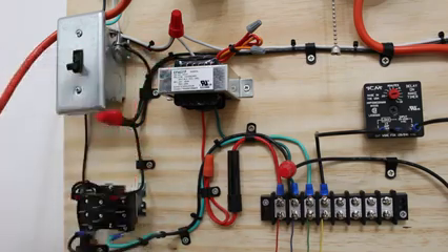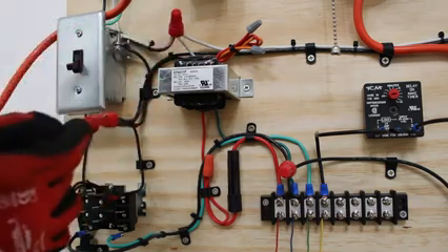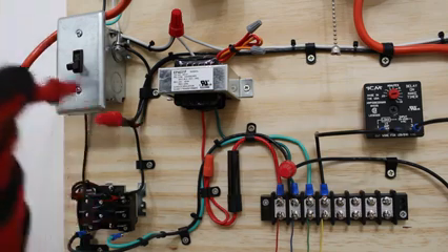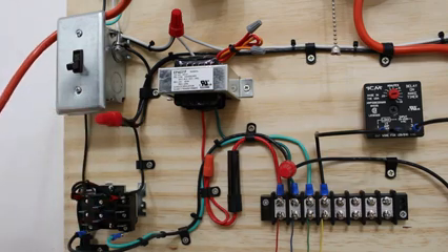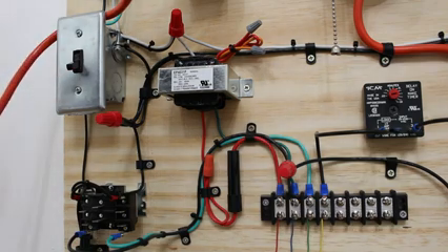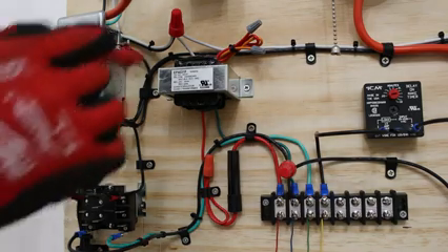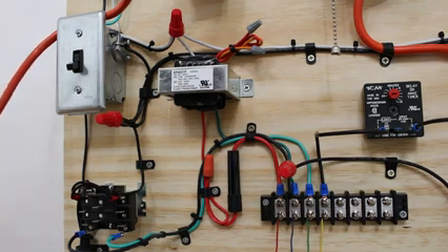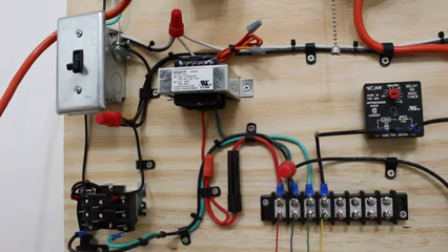It's all about making sure if you have your primary and secondary voltage. So if you don't have voltage at your primary, you need to stop what you're doing. It has nothing to do with the transformer. You need to look into the incoming power to the system. That means you're not getting incoming power. You got to follow those wires. So those are a couple tips, but pretty much that's what it is. Make sure you got your primary, make sure you got your secondary. If so, you have to go about things with the clues that the control circuit gives you.